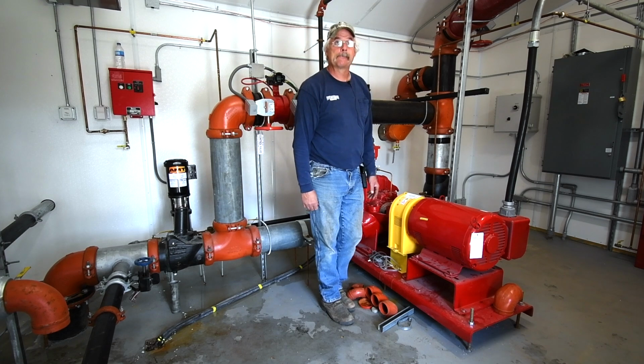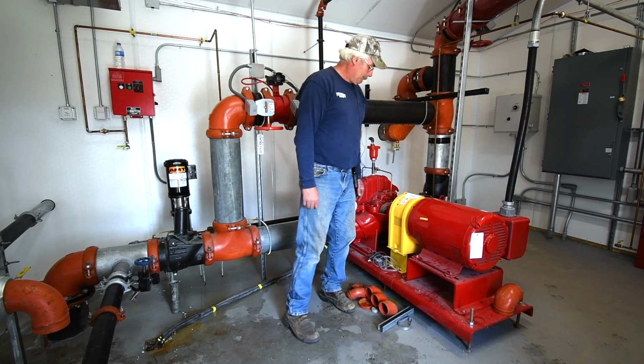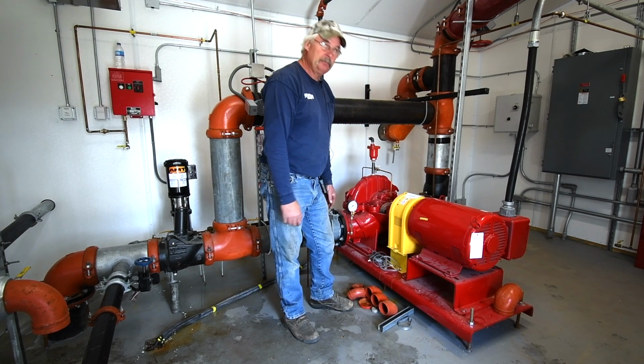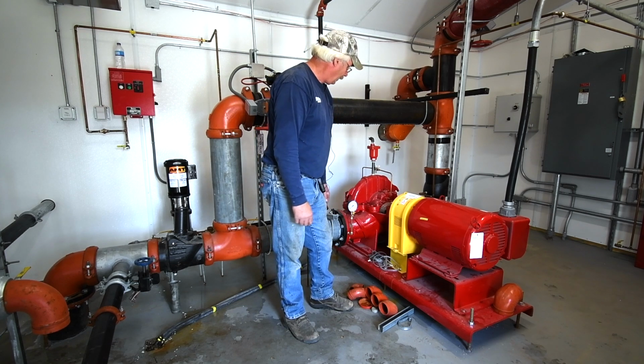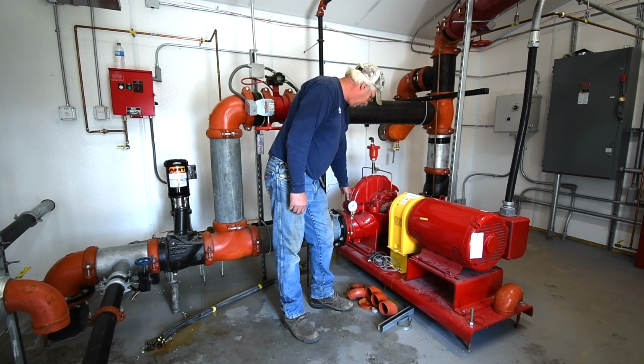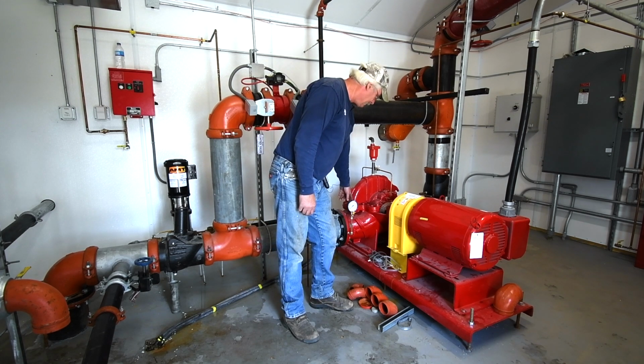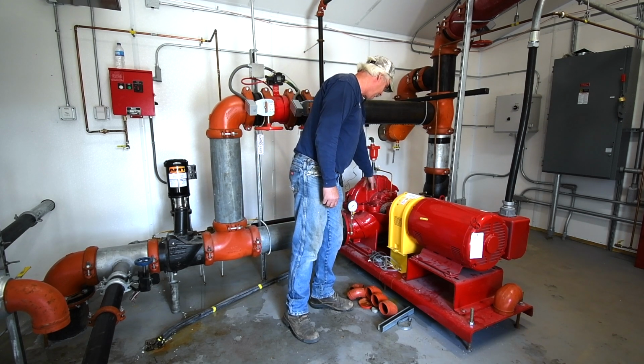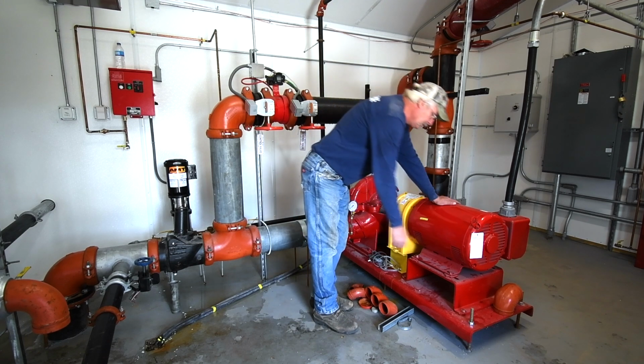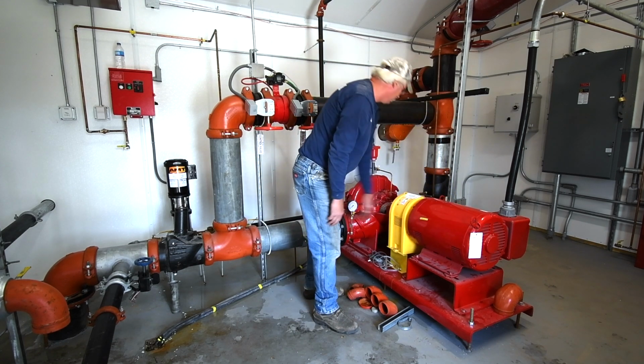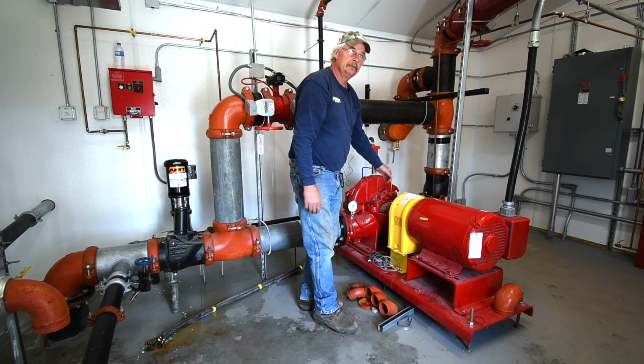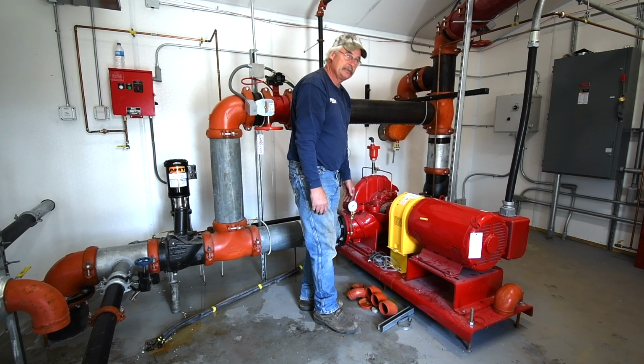Okay? Maintenance? Annual maintenance is we do the pump test, and we'll be doing a churn test, 100% and 150%. We'll be checking the packing, greasing the zerts. There's a grease zert for the motor. We'll make sure the pump's in line. We'll be doing pressure checks.